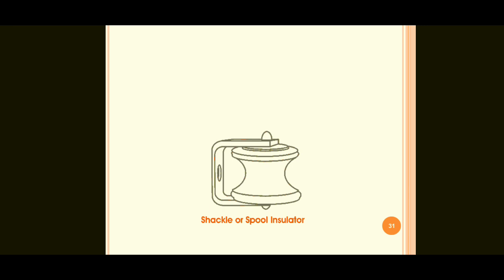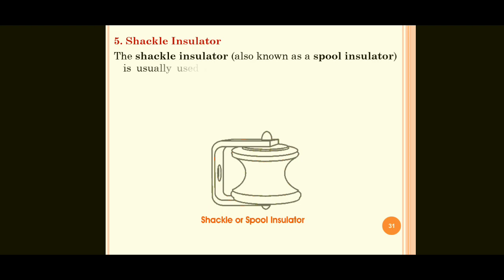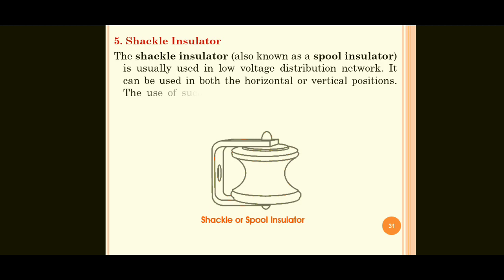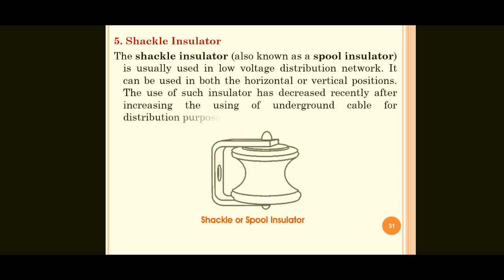Next one, shackle or spool insulator. The shackle insulator, also known as spool insulator, is usually used in low voltage distribution networks. It can be used in both horizontal or vertical positions. So we can place it either horizontal or vertical. The use of such insulators has decreased recently after the increasing use of underground cable for distribution purposes.